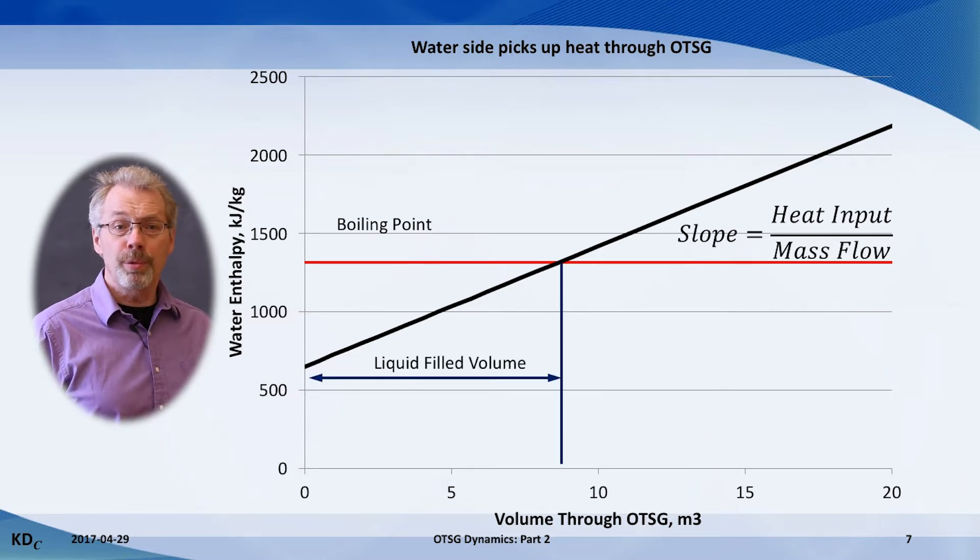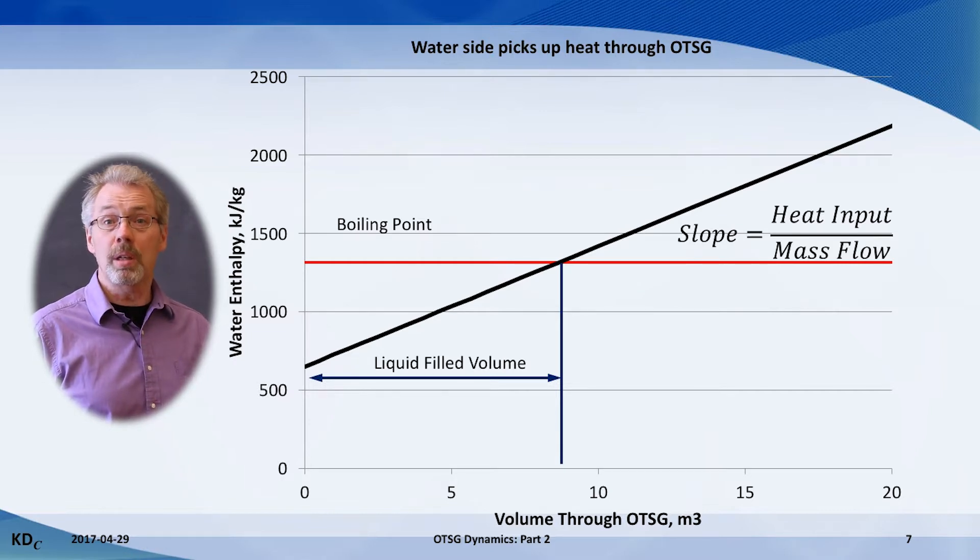The water-filled volume is that which is upstream of the boiling location. The volume downstream of the boiling location contains mostly steam. We are interested in what happens when the operating conditions change. These conditions are a change in firing rate, a change in water flow rate, or a change in feed water temperature.